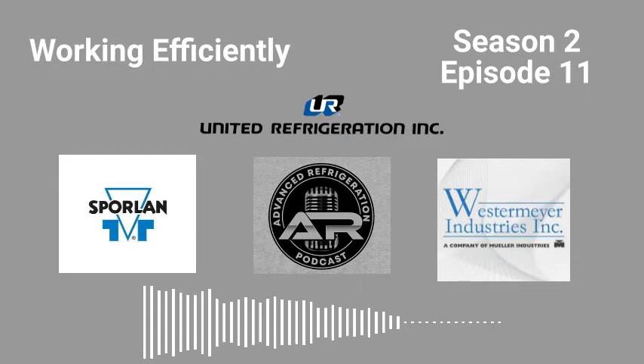Someone didn't actually believe me. They were filling up a rack. I told them to take the 3 or 4 cans and put it downstairs. He was on there for probably a good 40 minutes, metering the refrigerant through a Schrader. I'm like, how much did you get in? Because I'm waiting upstairs to see the receiver level. He says, I haven't got the first can in. I'm like, pull the damn Schrader. It's a no-brainer. You can fit a tank of gas in probably 2 to 3 minutes, depending on if it's a low or medium temp rack, if you just take out that Schrader.